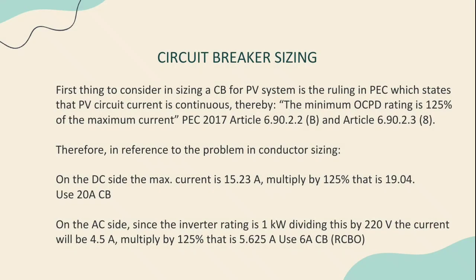Circuit breaker sizing. First thing to consider in sizing of a circuit breaker for photovoltaic system is the ruling in PEC, which states that photovoltaic circuit current is continuous. Thereby, the minimum OCPD rating is 125% of the maximum current. PEC 2017 Article 6.90.2.2 (B). and Article 6.90.2.3 (8). Therefore, in the reference to the problem in conductor sizing, on the DC side, the max current is 15.23 ampere multiplied by 125%, that is 19.04, so we can use 20 ampere circuit breaker.